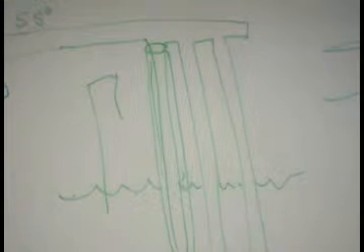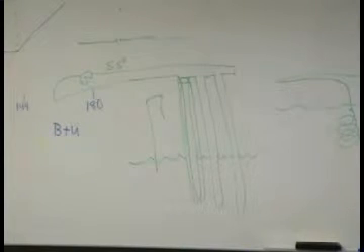Other stuff, that's geothermal, and that's ideal if you can do that, because that is free. All you got to do is pump it. Other than that, it's free. If you don't have something like that, you're going to have a source of heat and a source of cool. Source of heat is usually a boiler. So as we're sucking heat out of that loop, we're going to have something to put heat back into that water again. And so it's usually a boiler. In the summer, when we're heating the loop, we'll usually have a fluid cooler or a cooling tower to cool that back off again.